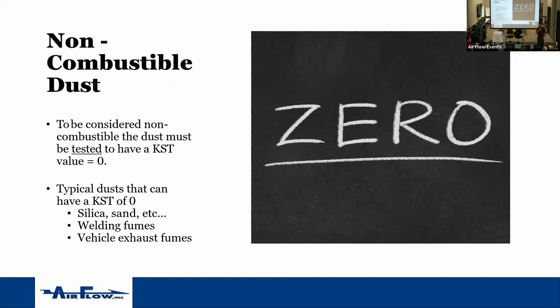Non-combustible dust. There's only one way that anyone here can determine if your dust is not combustible, and that's to get it tested. If you have a KST of 0 and you assume that you have a KST of 0, or your owner is telling you, hey, we've had this dust, we've been doing this for 50 years or 100 years, we've never had a problem, it must be non-explosive, get it tested.